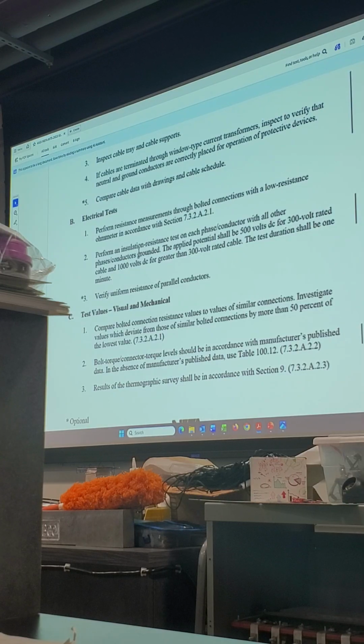So we have a data trend that can be looked at year over year. You might need to escalate your 5-year PM and test it yearly instead. If the numbers change after that, you'll want to test every 6 months. And if it gets closer still, during the next large turnaround you might want to take that section of the plant out of service to change out your fried cable.